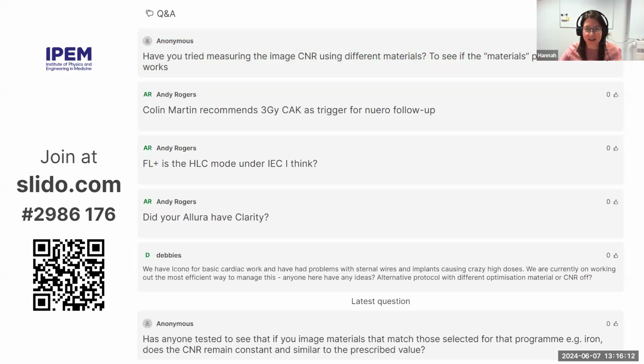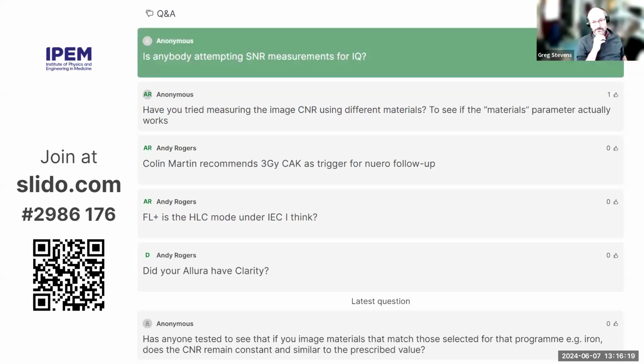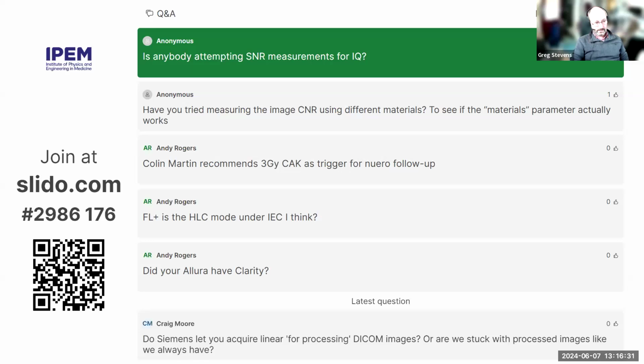Either of you doing SNR measurements for image quality? Or are we still doing the... You can't. You'd need to get linear data. So we did ask Siemens for the NEMA standard, XR27, I think it is, which allows you to collect linear data, which would allow us to do SNR or CNR measurements. That's not been forthcoming, unfortunately. NEMA is an American standard, obviously, and like Siemens said, it's not required in Europe. So that's kind of where we sit at the moment.